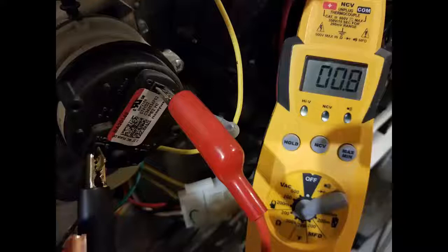If your meter indicates an open circuit or it is erratically jumping around, you either have a blocked or restricted exhaust or intake, a problem with the inducer motor, plugged or cracked pressure tubing, or a bad pressure switch. Now we'll watch a quick video of the process actually taking place.